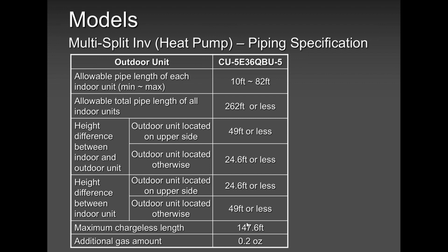But guys, remember the unit is only charged for 147.6 feet for this model, for this 36,000 BTU. If you're installing a 2-zone, a 3-zone, or a 4-zone, it's different. But the 82 feet remains the same. 262 feet also remains the same. Height difference also remains the same with other models, especially on the multi-zones, okay?